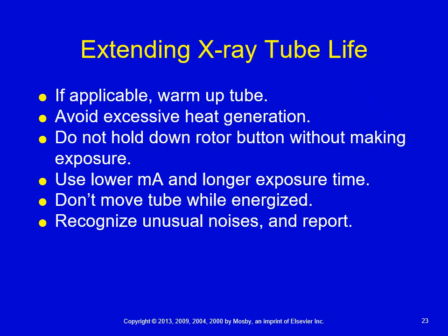All right, avoid excessive heat generation. So to do that, one of the things that we don't want to do is hold that rotor button down unnecessarily. Some instances where we use the rotor is maybe we're trying to x-ray a kid that's really squirmy, or a patient that's really in pain.